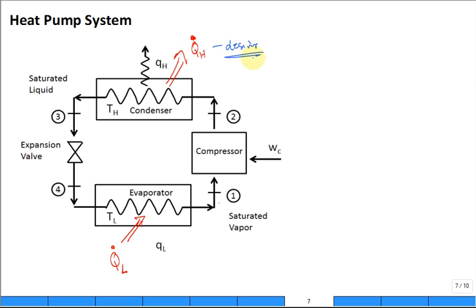Where do we find heat pump systems? You could buy a residential heat pump system and it's like an air conditioning system run backwards where inside your house you don't have the evaporator, you have the condenser. And that makes, as the air flows over it, hot. It makes the air hot and then in the winter that's dumped into the bedroom and the kitchen and different parts of the house, the living room. The outside unit is now the evaporator.